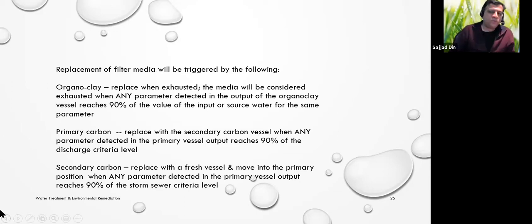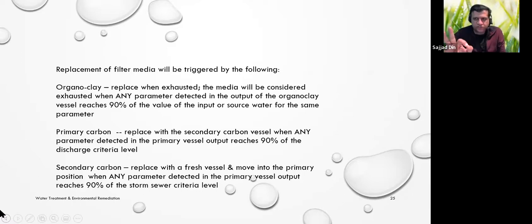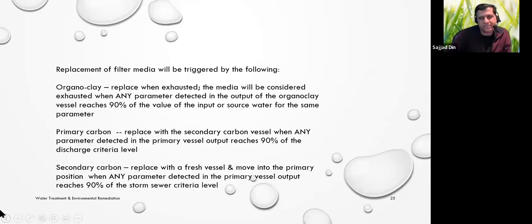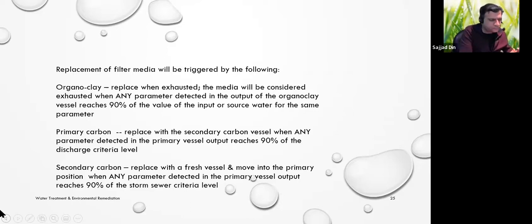When monitoring, we check whether the carbon needs to be replaced — after it removes enough contamination, it needs replacing. We have carbon vessels in series because we don't want even the slightest chance of contamination reaching storm or sanitary sewers. The difference between them is that sanitary sewers go to a wastewater treatment plant, whereas storm sewers go straight to a natural surface water body.